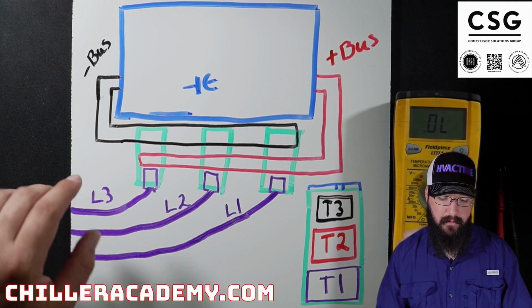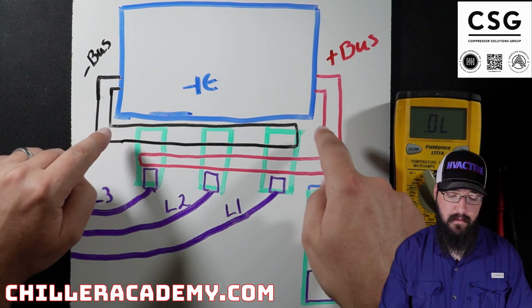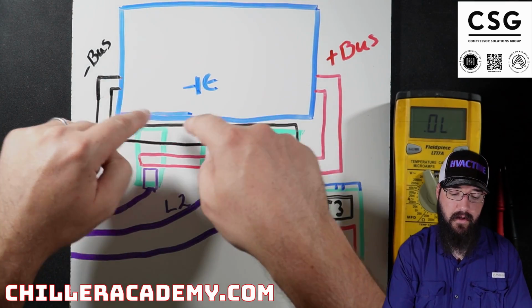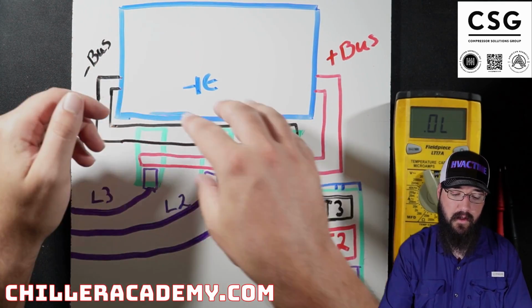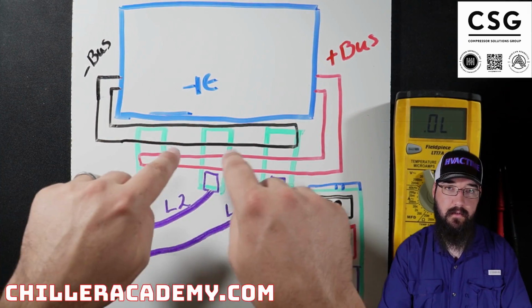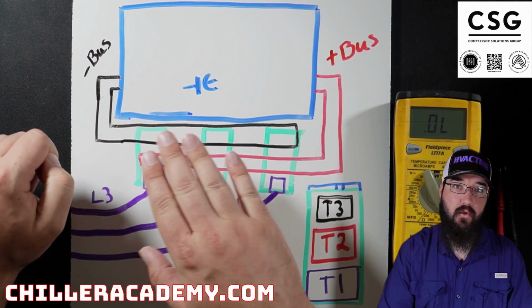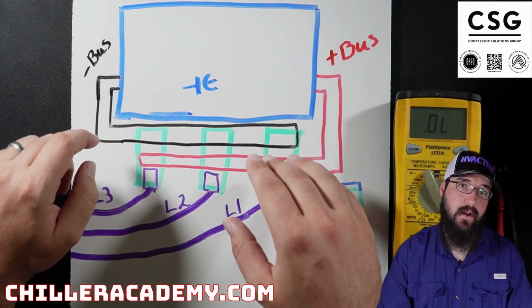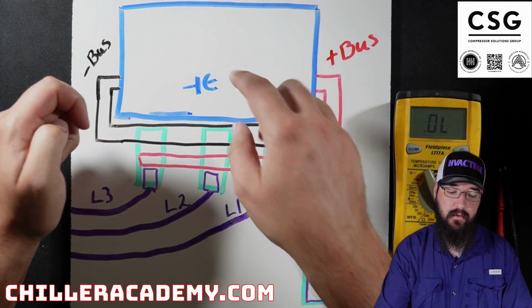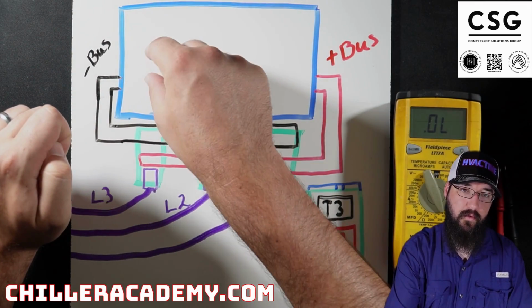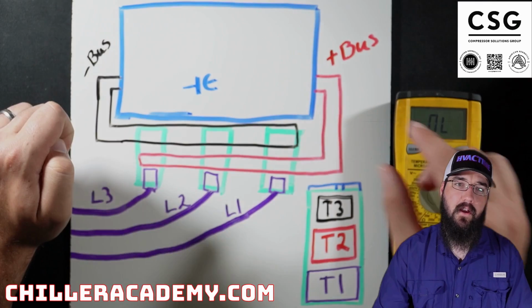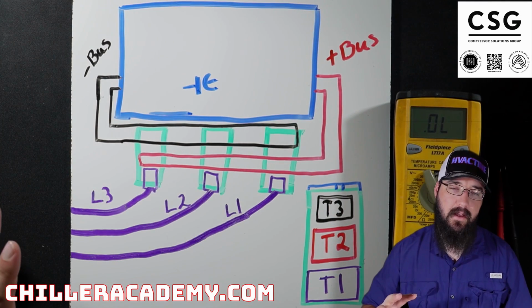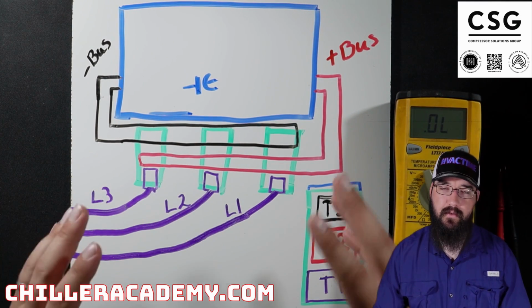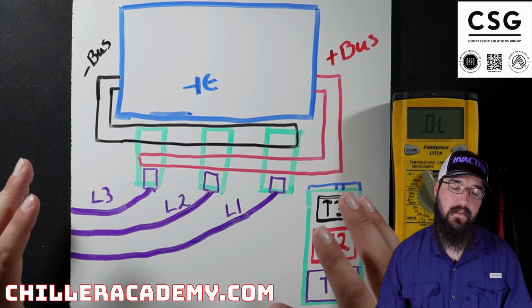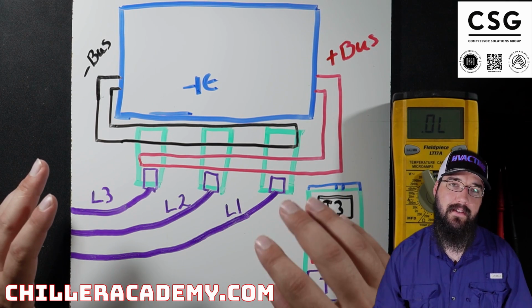To verify that, you can test across this bus. You can test across the back of your IGBTs, so those will be sitting up on top of where these SCRs mount. These mount to a cooling plate, and above that is your IGBT assembly. The back of those terminals, or if you find two terminals close together back here on the capacitor bank, you can test across your capacitor. So there's several places you can look at to see what your current DC bus voltage is.